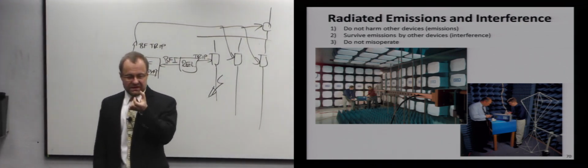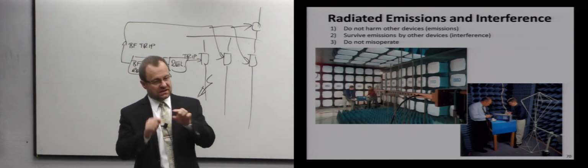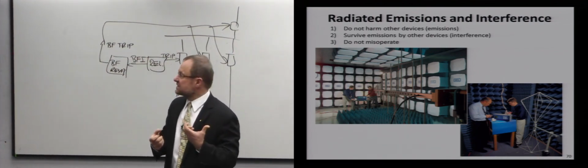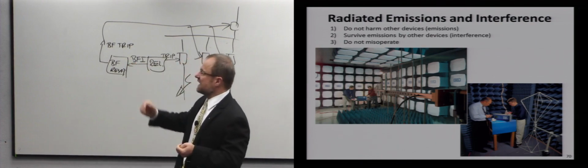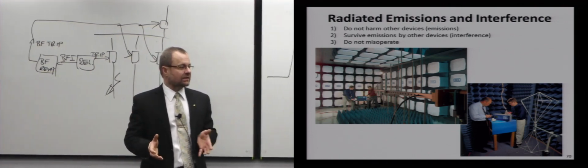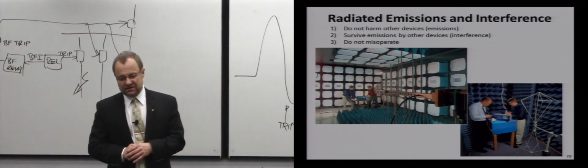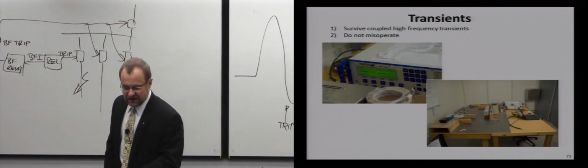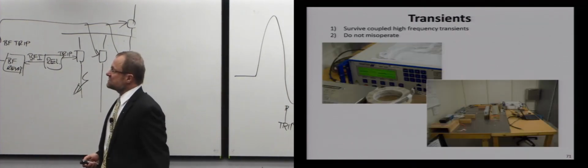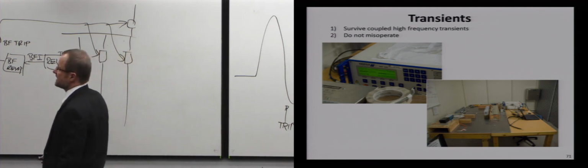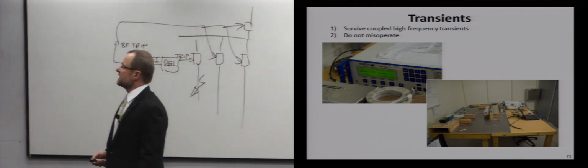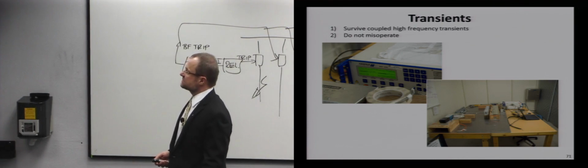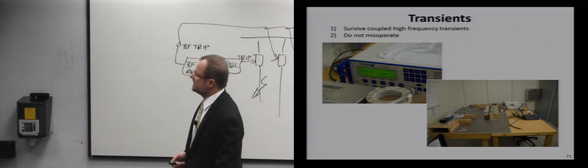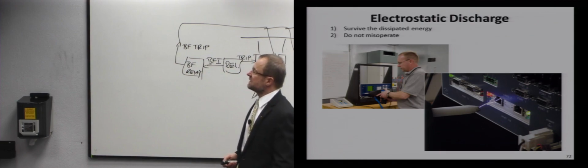The length of the leads, and we have to put certain things in cages and shield them because we are emitting. This is our old lab. Right now we have a lab that you could bring a big truck into and it will fit in the new building. So we are investing in that equipment. Transients, things couple through wires. So there are IEEE standards for how you hit the device with various transients, and it should survive, it should not misoperate, and so on.